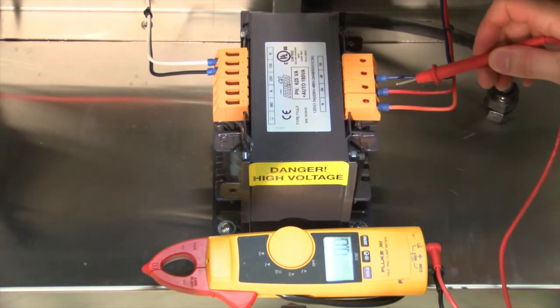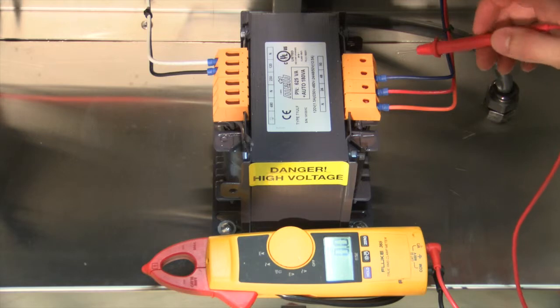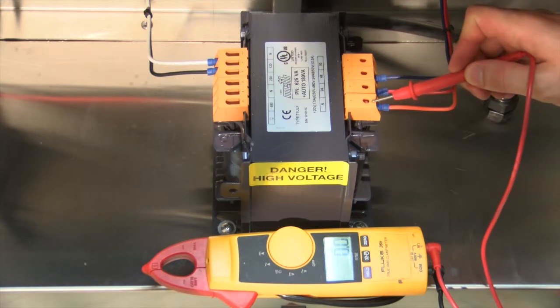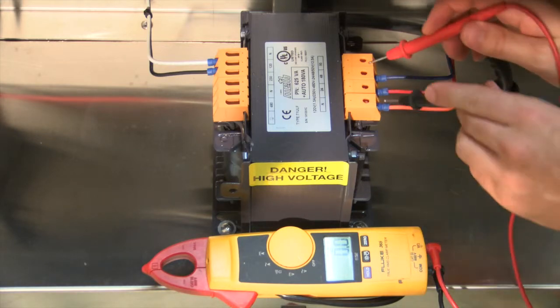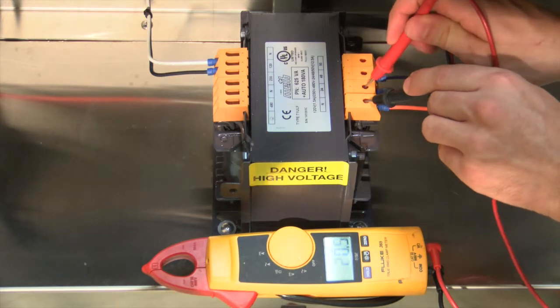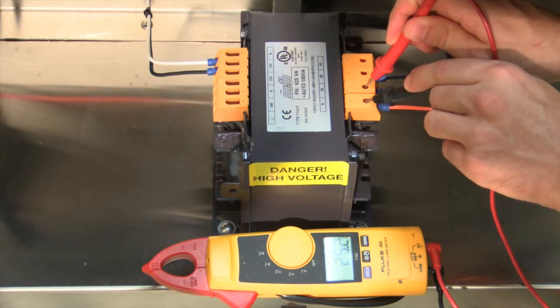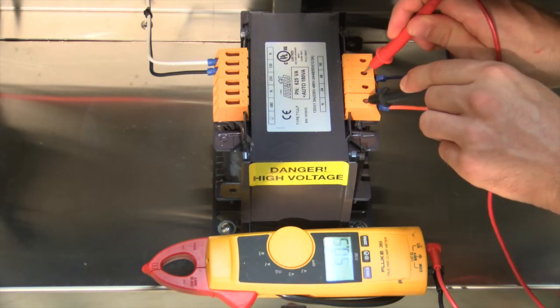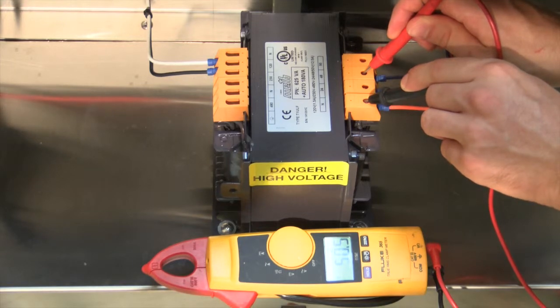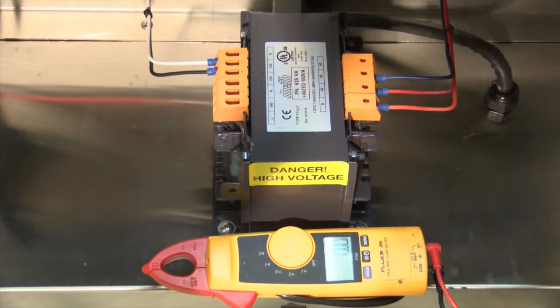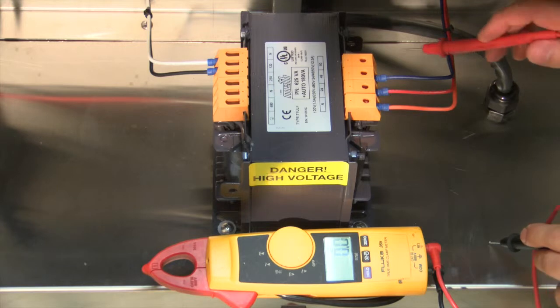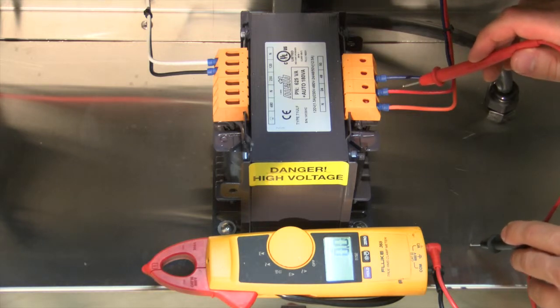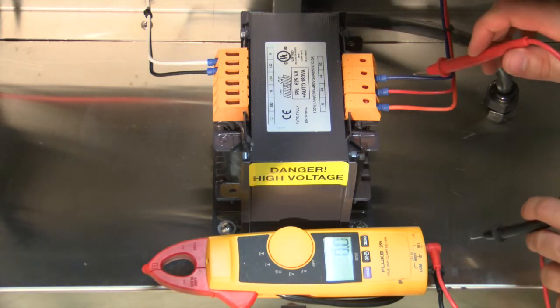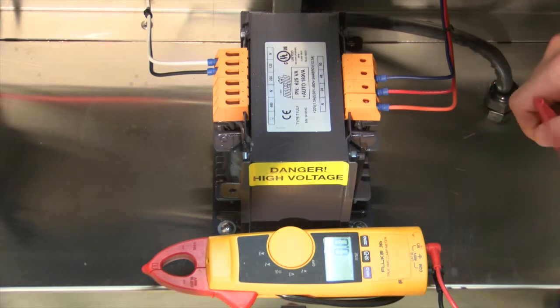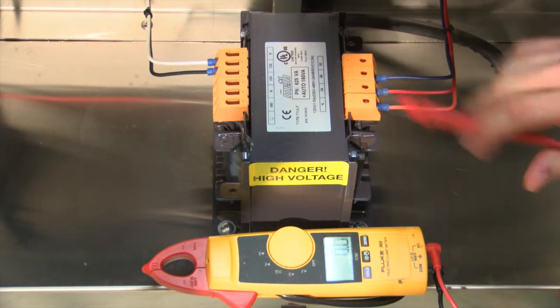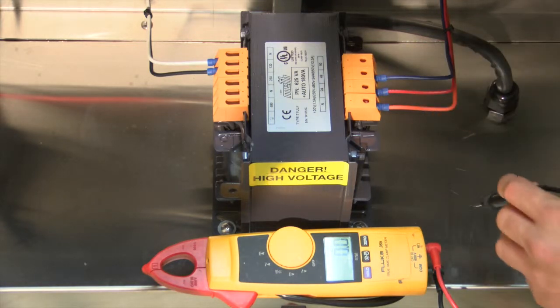On the secondary side of the transformer, you must use the secondary neutral to get an accurate reading. In this case, we'll take a 24 volt reading on the red wire and a 48 volt reading on a blue wire. Taking a reading on the secondary side of the transformer against ground will not give you accurate readings. We'll show you this now when the transformer is drawing.